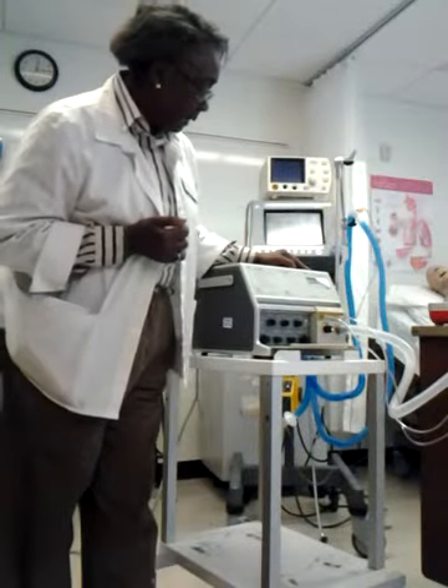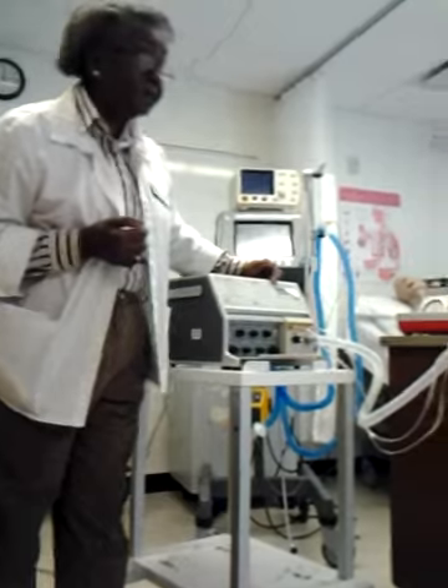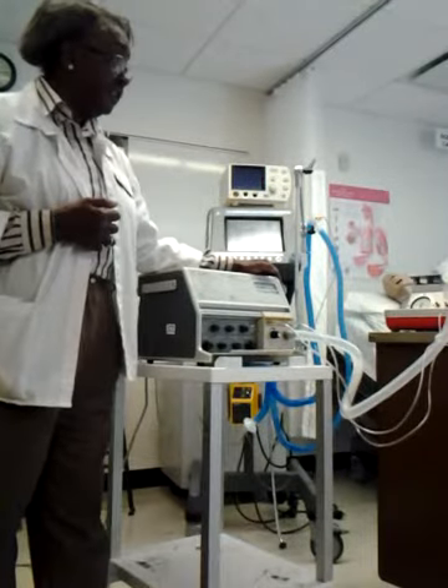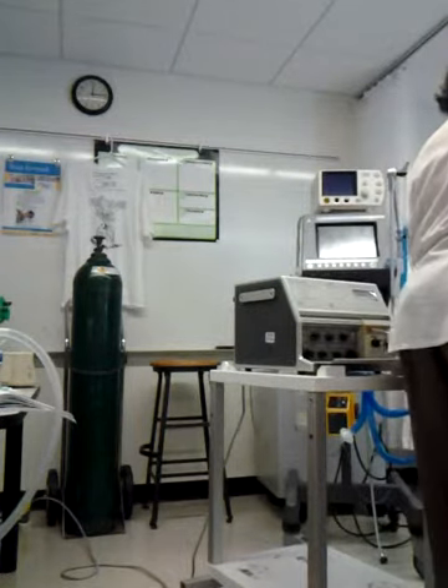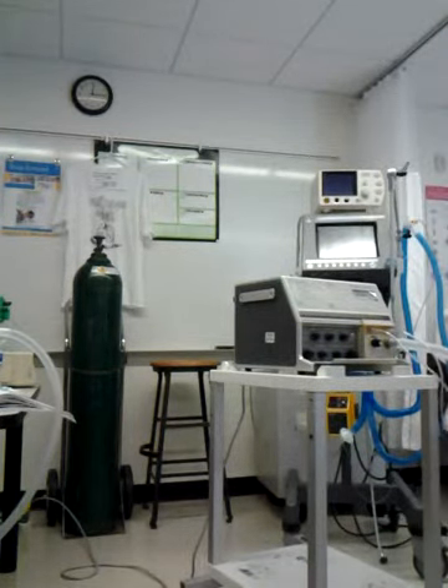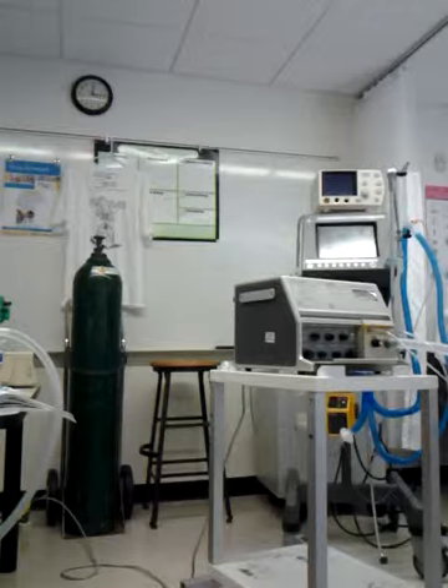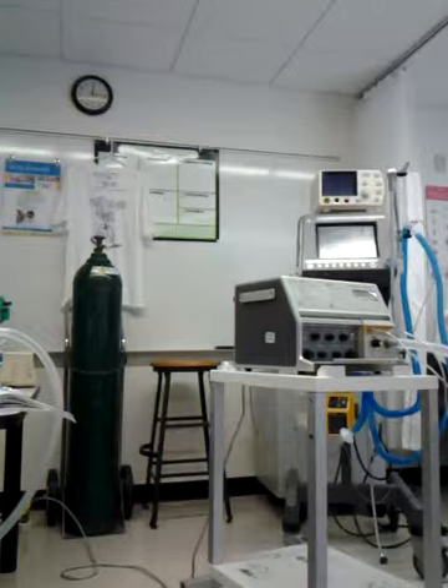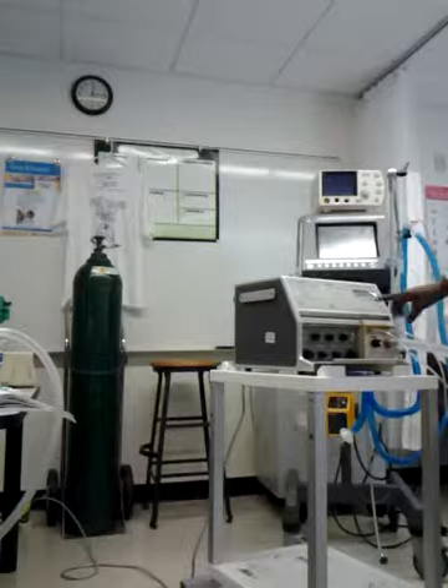Okay, now, if you notice, my pressure manometer is going to 0 on every breath. If I want PEEP, I have to attach my PEEP valve, and as I'm turning it down, you'll notice that my PEEP doesn't go back to 0. It stops at whatever my PEEP pressure is. So you actually control the PEEP externally, and you can tell what PEEP your patient is getting by looking at your pressure manometer.